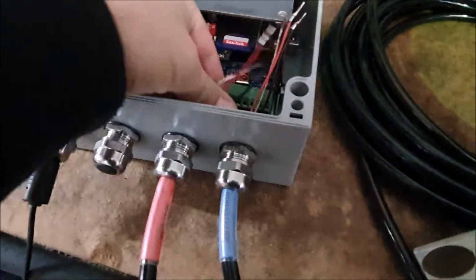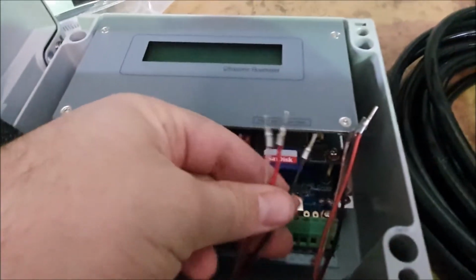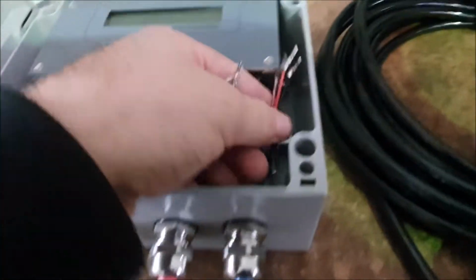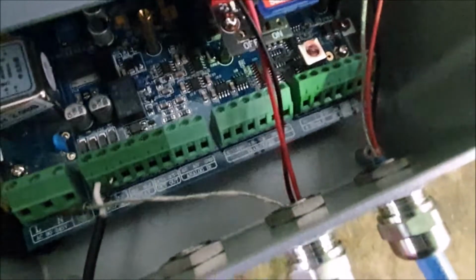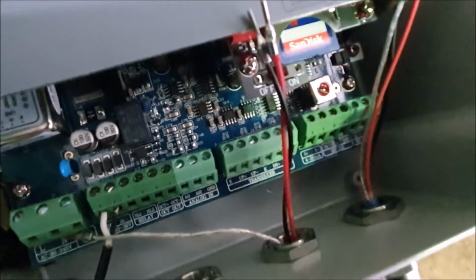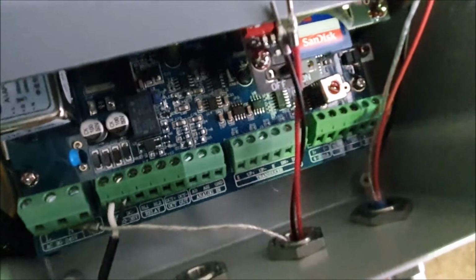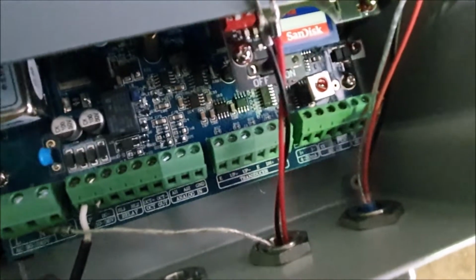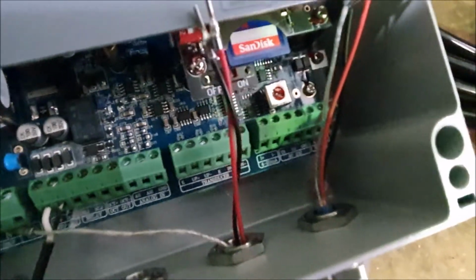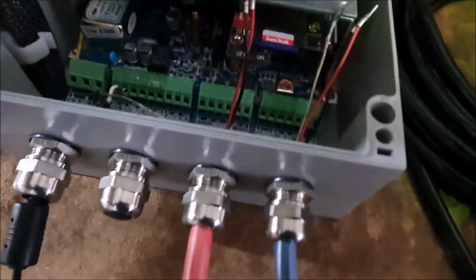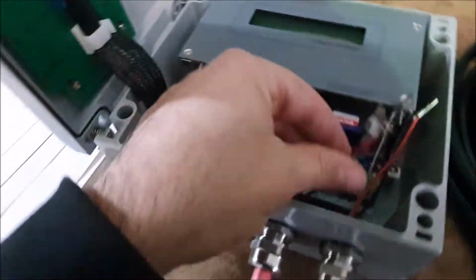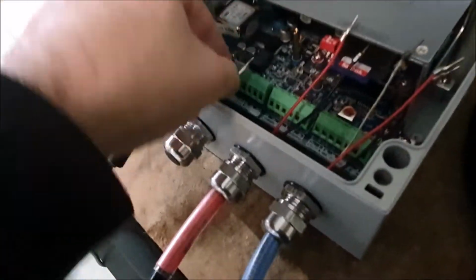Now, terminating your cables, they've already got nice end pieces on there for termination on both, and we just want to install them into the section that says transducer. Okay, it's going to be a little hard to see here on camera, it's dark, but you've got an E, an up plus and an up negative, and then another E, a DN plus and a DN negative. Okay, so up is obviously upstream and DN is downstream, and then we just got to put these cables in.